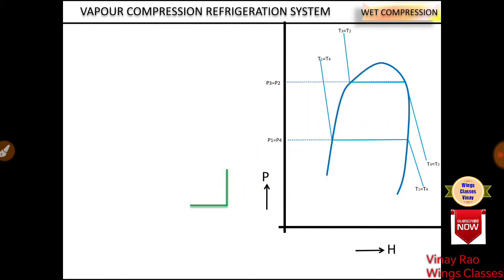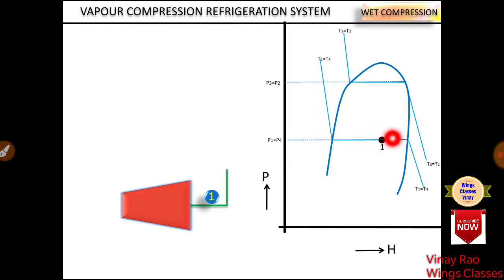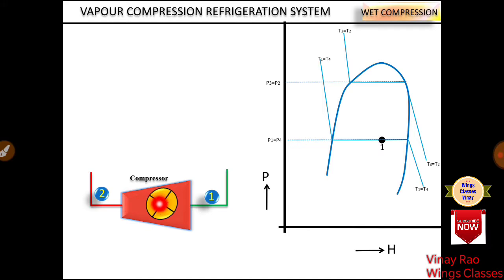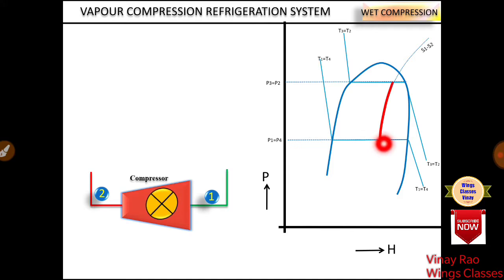At point number 1, pressure is P1 and temperature is T1 along a constant temperature line. From 1 to 2 there is a compressor working on an isentropic process, meaning entropy is constant. In the P-H chart, entropy lines appear as inclined curved lines. From 1 to 2 we follow the isentropic line where S1 equals S2, giving us point number 2 at a higher pressure.